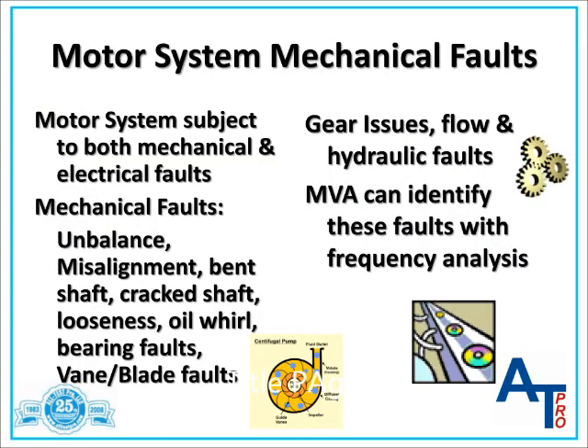The electrical motor system consists of the electrical and mechanical subsystems. The mechanical subsystem consists of the motor shaft, coupling, driven machine, and the process itself. Since all of these components are mechanical in nature, they are subject to any fault associated with the rotating machine. Faults such as unbalance, misalignment, bent shaft, cracked shaft, mechanical looseness, oil whirl, rolling element bearing faults, vane passing forces, gear meshing, flow, and other hydraulic faults are identified using MVA if the force is strong enough.